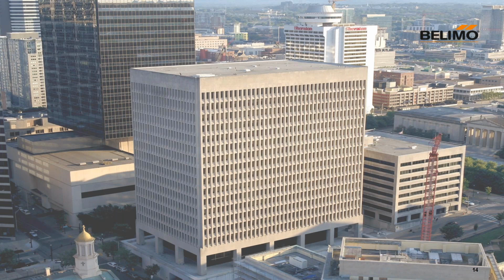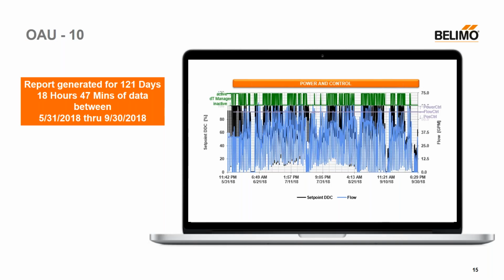In the bottom of this one, it's actually in the parking garage downstairs, there is a large meter and we could see the flows and the delta T of the building. So throughout this project, we were able to even get a real check-in from the building of what was going on. We were able to also constantly download data. So this is one example of data we downloaded from one particular unit in 2018. This is looking at essentially July through September of 2018 of one particular valve.